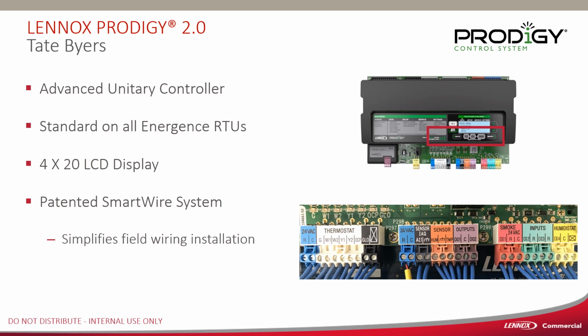You will look at the wire, you'll see 2 chevrons pointing in one direction. Tucked in there, it may say J110-5. That would be jack 110, pin 5. Next to that will be 2 chevrons pointing in the other direction. That may say P10-3. That would be plug 10, pin 3. Every 4 inches it's labeled where each end of the wire goes. There is no reason to start cutting all the wire ties when you're tracing wire and servicing this machine.